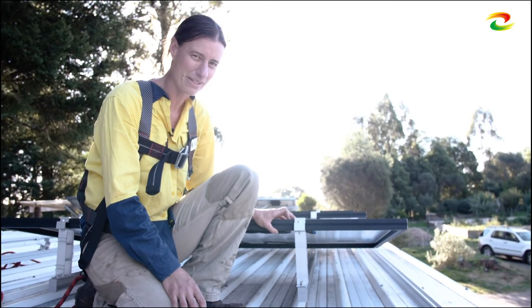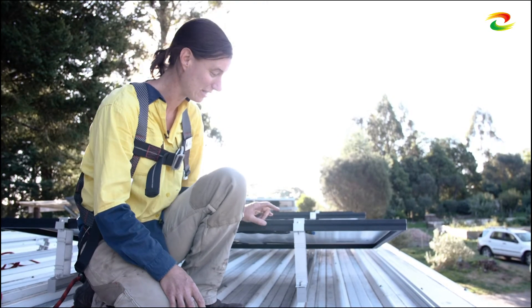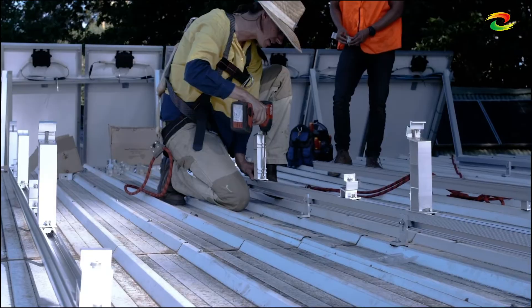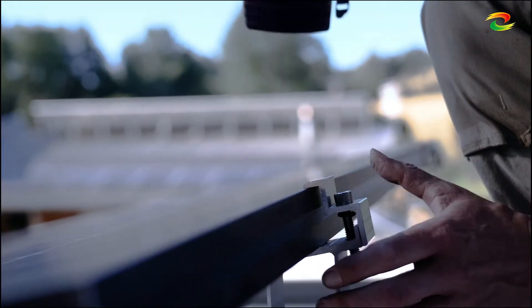It is similar to some other brands that I've installed, but it has some nice advantages — particularly that adjustability by using the L foot and the moulded rail, and also the bit that bites in there so you don't need an earth wire. Yeah, they're good.